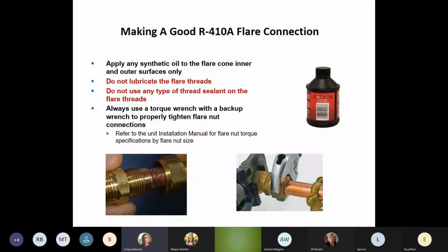But you need the right flaring tool, 45-degree flare. If you have torque wrenches, let's get the torque wrenches out. The manual tells you what that nut should be torqued down to. Like I said, if you're going to get a bigger wrench, that's not fixing the leak. It might be causing more of a leak. We're going to mushroom the flare. We're just going to cause problems.